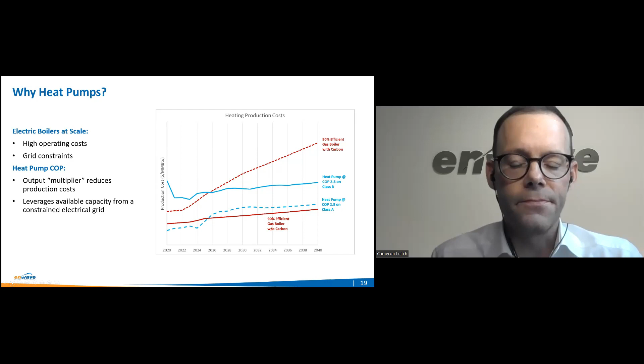This chart shows a representative forecast of cost per unit energy produced over time in the Ontario market. The two blue lines are the production cost for a heat pump plant with a COP of 2.8. Class B is Ontario's flat but higher electricity rate. Class A is an industrial rate that charges customers based on their contribution to grid peaks, and the curve shown here assumes the heat pump plant avoids those peak charges. The bottom red line is the base production cost for a 90% efficient gas boiler without carbon pricing, and the dashed red line shows the total production cost for the same boiler, including carbon pricing. The main takeaways are that even now, a heat pump plant on a Class A rate structure has the potential to produce heating at lower costs than the natural gas alternative, and within the next 3 to 4 years, even the flat Class B rate structure will become competitive. Next slide, please.